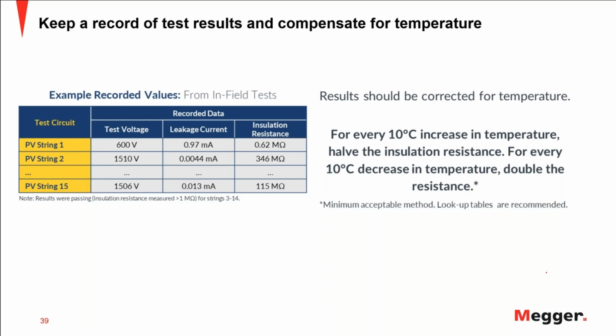Well, I think I'm running out of time, but this is showing an example of different strings, and you have not only the result, a low result. You should not always look only at the actual resistance value. You should look at the voltage. If the voltage you intended to run the test at is not achieved during the test, it also tells you that it's a result that is not valid.